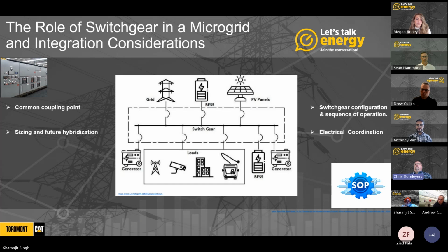The overall control system integration often must be reviewed in conjunction with the switchgear requirements. Depending on the application and sources connected to the switchgear, specific protective options may need to be selected when formalizing the design. For example, local utility requirements need to be considered when scoping out the switchgear requirements. It should be noted that when specifying requirements for the switchgear, utility requirements should be identified as the initial step. These are all things the integrator looks at to ensure the control system and other elements of the system are matched to deliver maximum performance.